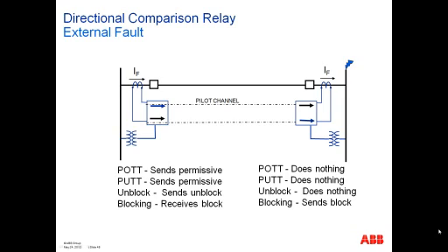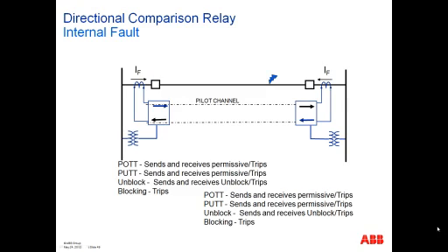And then a blocking signal is received at the left end because the remote end sees a reverse fault and sends a blocking signal. So that's basically how they would operate for an external fault. For an internal fault, POTT sends and receives permission at both ends. PUTT sends and receives permission. An unblocked system sends and receives an unblocked signal and trips.